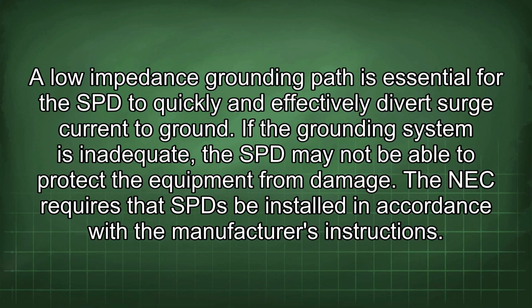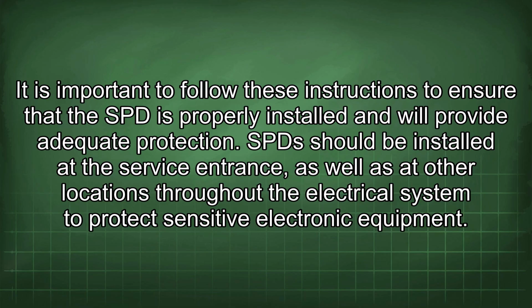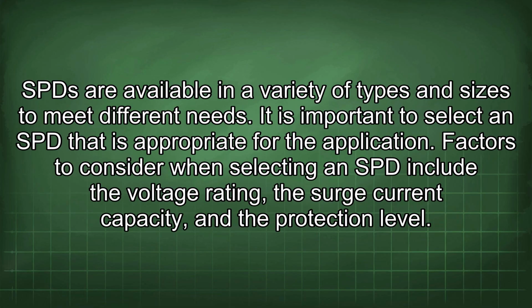The NEC requires that SPD be installed in accordance with the manufacturer's instructions. It is important to follow these instructions to ensure that the SPD is properly installed and will provide adequate protection. SPD should be installed at the service entrance, as well as at other locations throughout the electrical system to protect sensitive electronic equipment. SPD are available in a variety of types and sizes to meet different needs. It is important to select an SPD that is appropriate for the application.